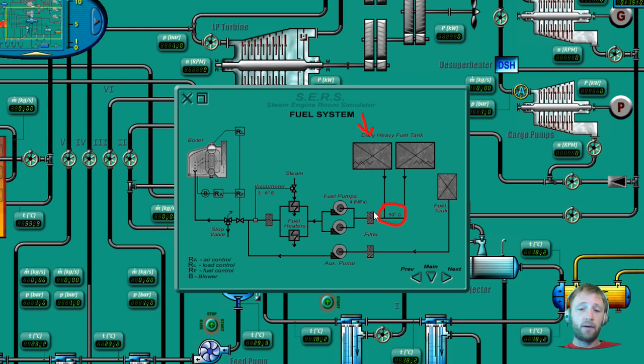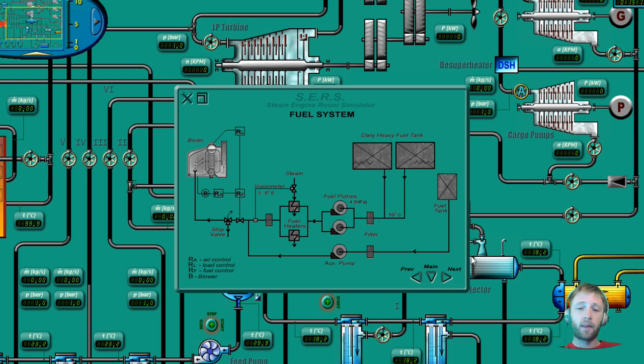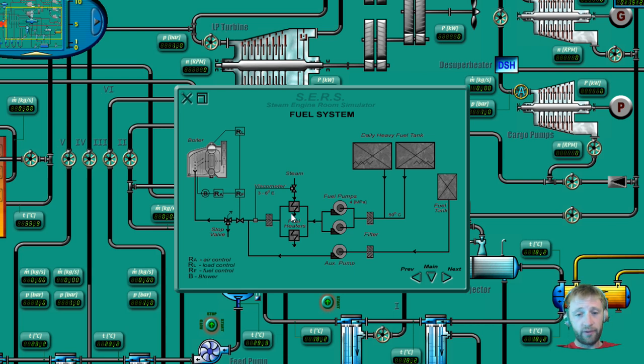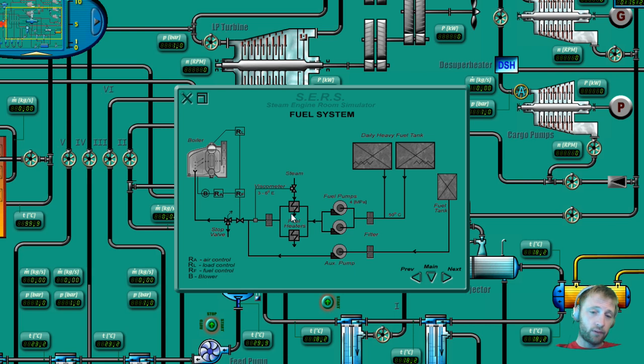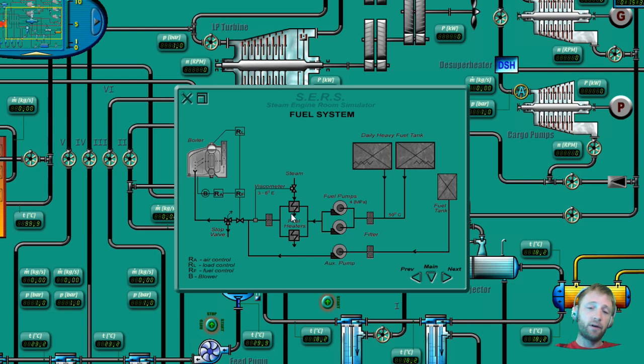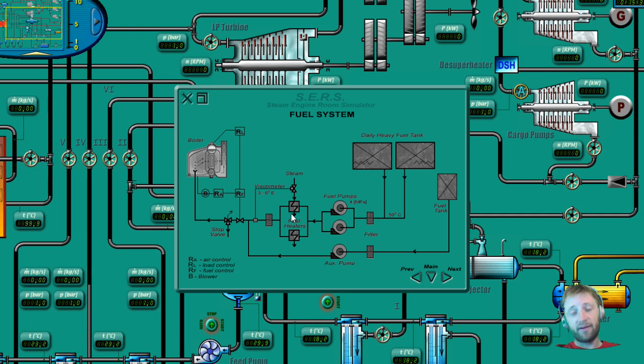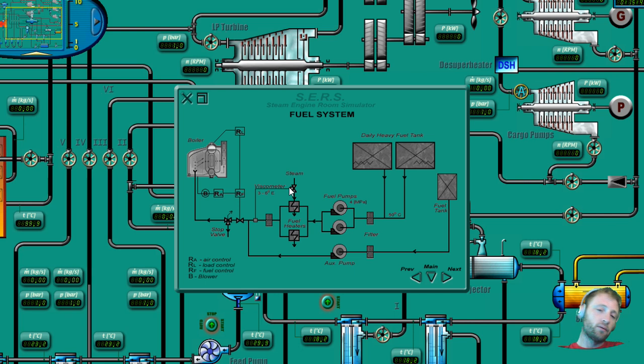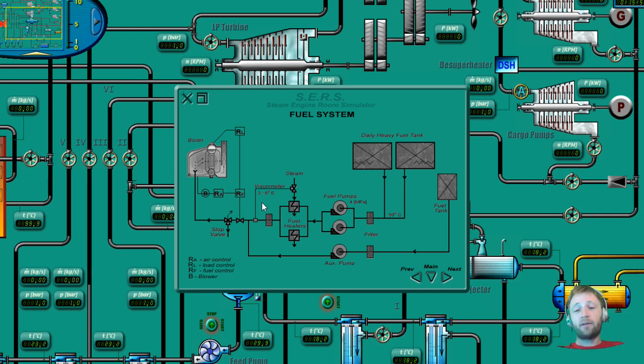And after that some filters passing, we have increase of pressure here from this point to 4 MPa. We have two fuel pumps. Then we have heaters again, which for sure increase the temperature of the fuel, depends of the quality of the fuel. And also it will depends from the viscosity which is needed by the specified fuel which we are bearing on our tanks.